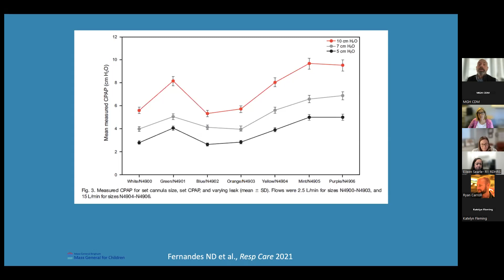Maybe another way to look at this is that the set CPAP of 5, 7, and 10 is below the measured CPAP on the left-hand side on the y-axis. With 0 leak, we pretty much achieve what we intend, and with 20%, 40%, 60% leak, we achieve near what we're intending. With 60% leak, for instance, we actually still maintain even more than 40% of what's intended. So it does a pretty good job. This was done without leak compensation, which most of our ventilators have to try to maintain that pressure. So just to say that these simple interfaces work quite well. But what's important, more than just the science, is how these are applied, how they're maintained, and how the airways are suctioned. So Krista will take us through that journey.